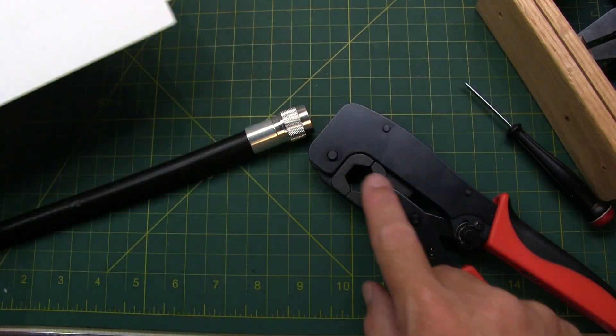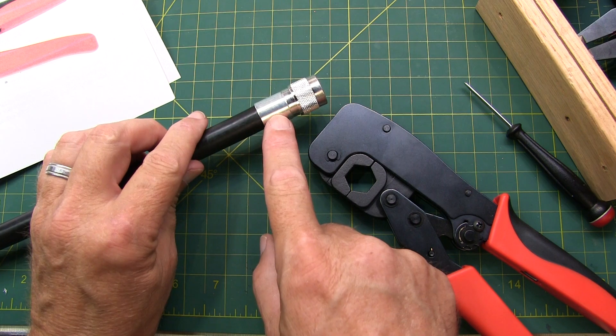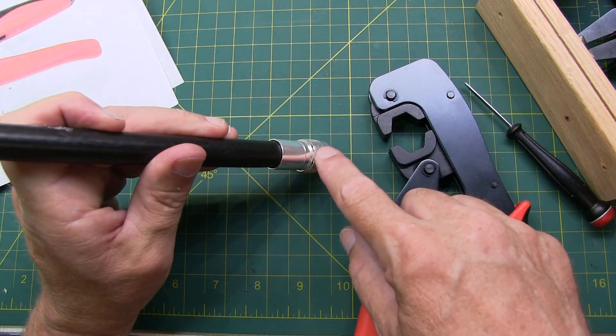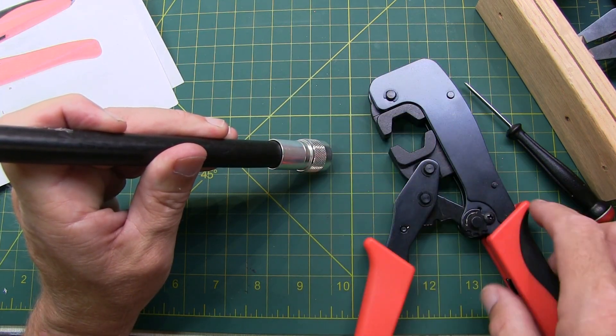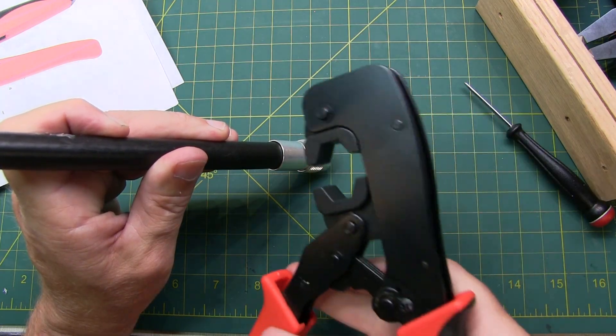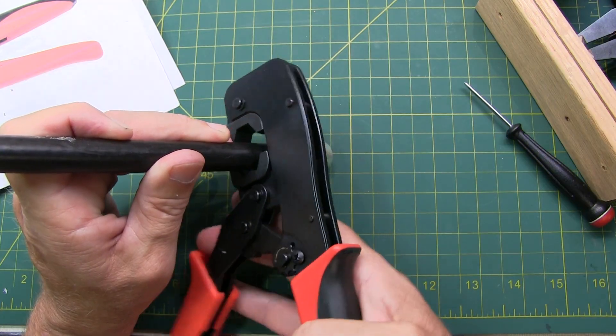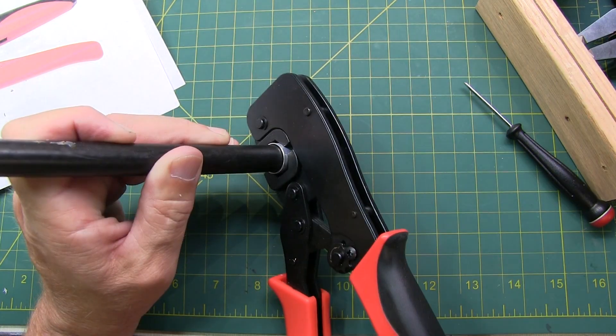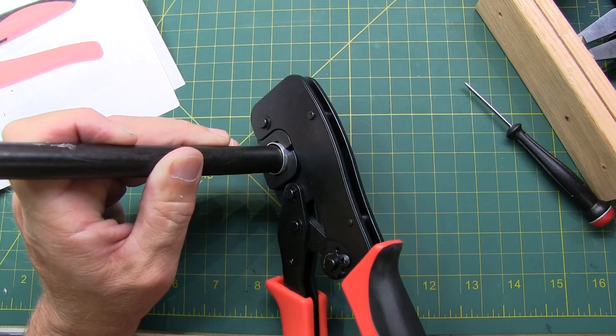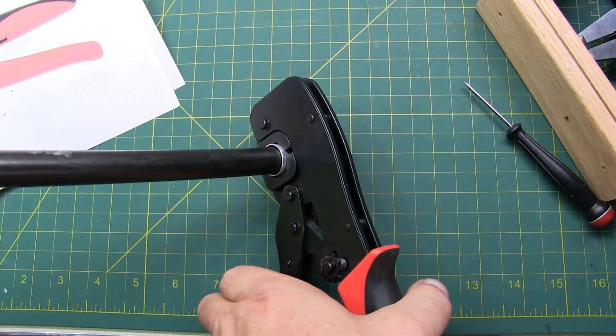And we use the matching crimping tool to crimp the ferrule. I'm keeping pressure on the connector onto the top of the table so that when I position the crimping tool, the connector doesn't back itself off. With the tool in place, we execute the crimp. Two-handed job.